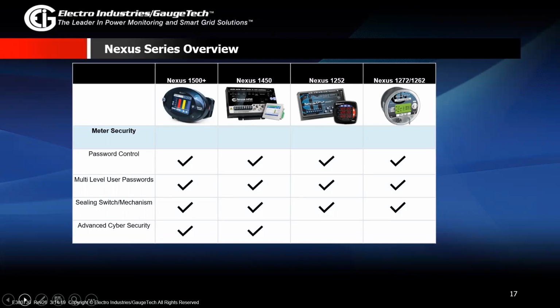So you have the option to put in passwords, not just for a single user, but for multi-level users. There are sealing switches and mechanisms to make sure that tampering is not possible. However, the newer Nexus 1500 Plus and 1450 meters actually have more advanced cybersecurity capabilities. And when I say advanced cybersecurity, I mean they have AES-based encryption. So all of your usernames and all of your passwords are completely encrypted, and there are also password fail timeouts.